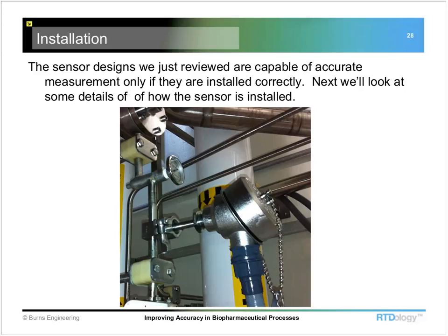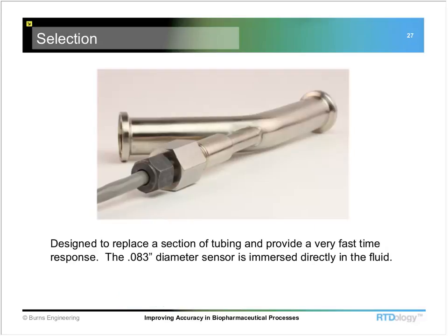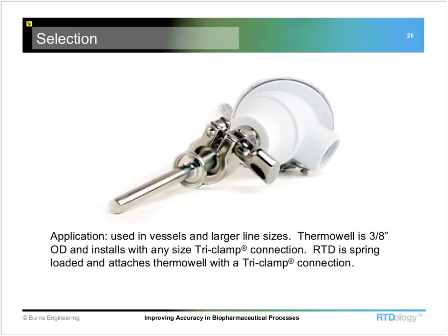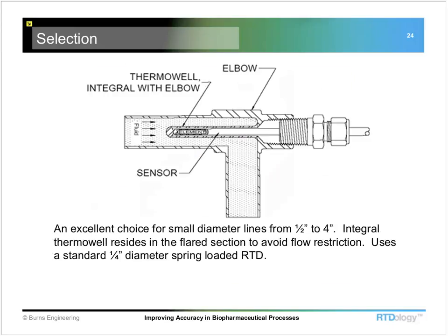Also, a comment about using heat transfer paste or silicone liquid to eliminate the air gap. Can you talk a little bit about that, Bill? Right. Yeah, this is a question I do get quite a bit. If we look at something like this, we can use a heat transfer paste in this type of RTD thermowell assembly.